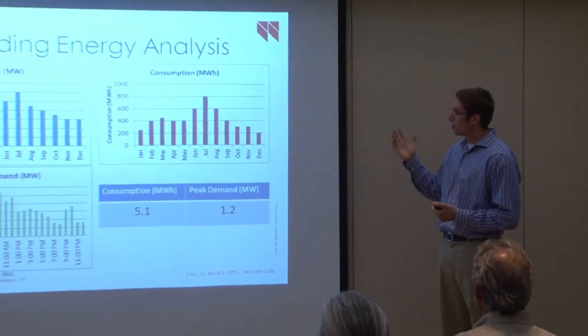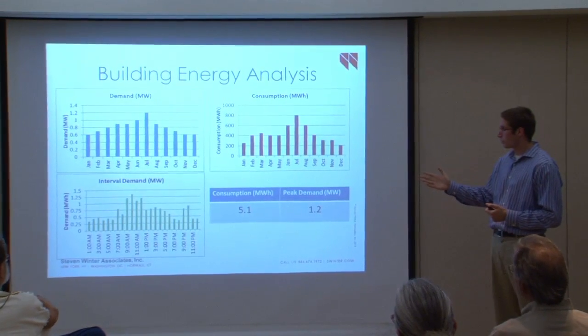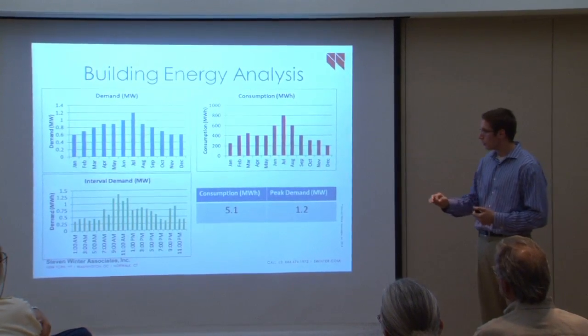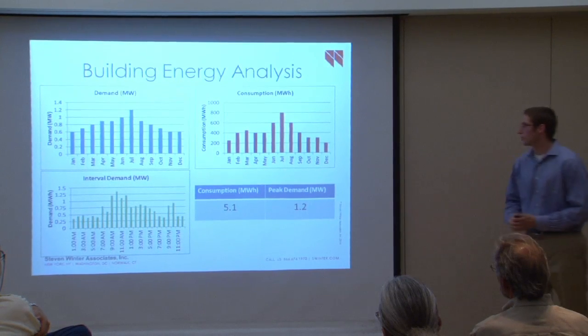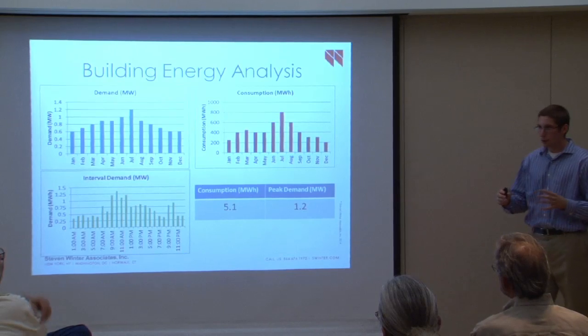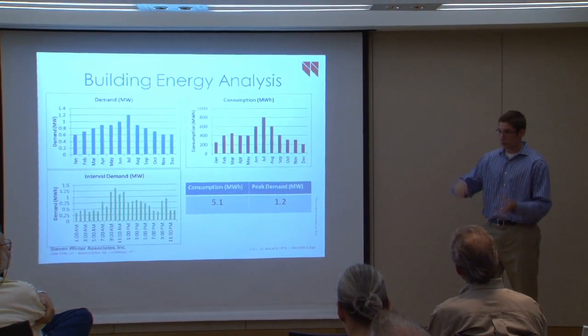Once you've selected your facilities, the next step is to look at how much energy they actually use. There are three different metrics that drive this discussion. One is the amount of demand power they use, generally regarded as the peak power consumption over a time period. In your utility bill, you'll see it monthly, but for this analysis we're also concerned with what it looks like on a tiny interval, such as hourly, because if we're incorporating something like solar, we need to know if the load is present when the solar energy is available.